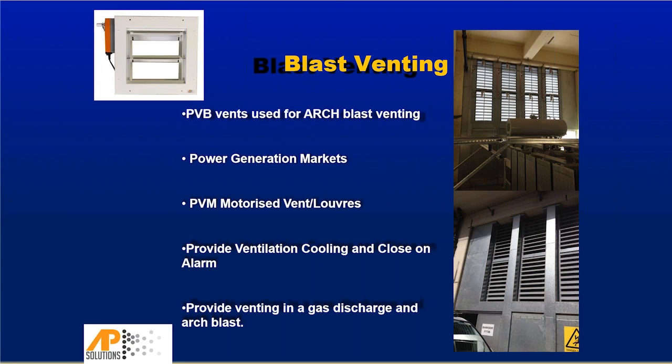This then moves into blast venting, and a couple of the pictures I show on this slide are of some pressure vent louvers that we designed for some substations around the UK. They are open normally for ventilation to keep the temperature down in the substations, but on activation of a fire alarm they will spring closed to allow fire suppression to be discharged into the substations. If there was a blast or overpressure caused by the suppression system, they will spring open to relieve that pressure and snap closed again. If there was a blast, they would open fully to relieve that blast and then close again.